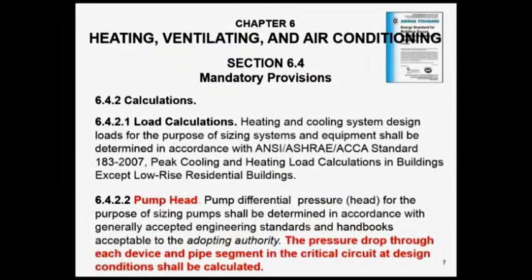The first thing we have to look at in 90.1 2010 and 2013 is what it says about pump head. Pump head is directly related to balance, directly related to energy usage, and we want to make sure you understand the connection, because we're going to be looking at pumps as we talk about balance. We're talking about hydronic balance today, not air side, just the hydronic side. Basically, what was new in 2010 was that for every pump, you had to calculate the pump head and the critical path in that building and find out where that critical path was and count every T, every elbow, every fitting, and that becomes your pump head, and you have to put it in a file.